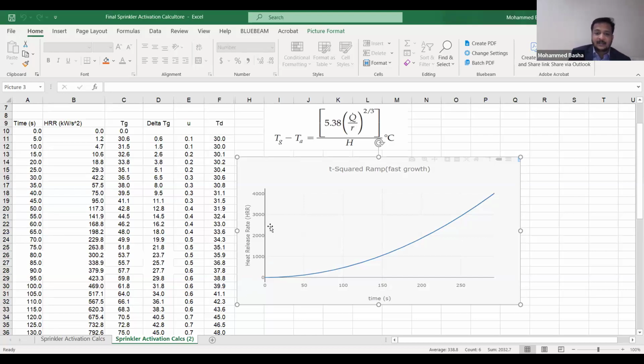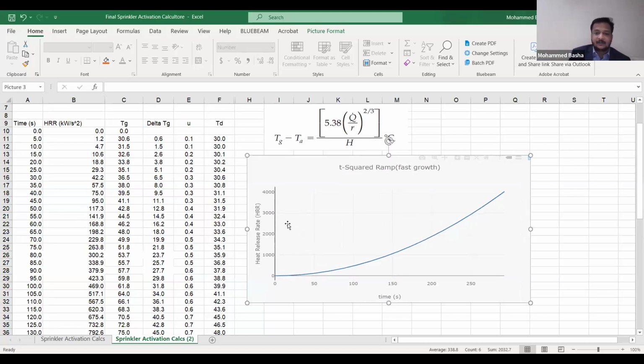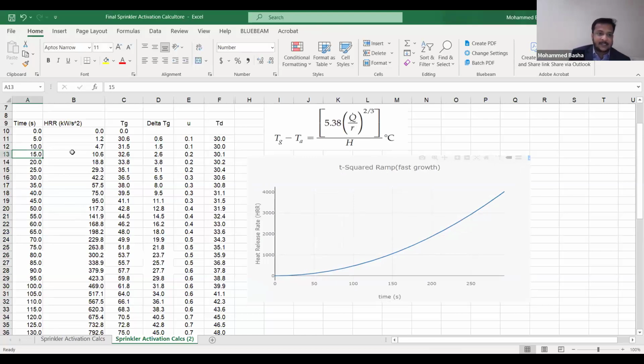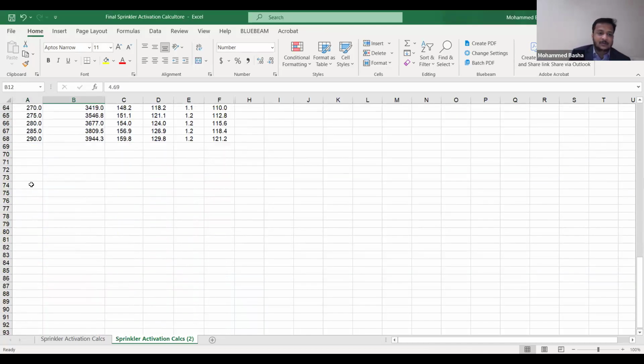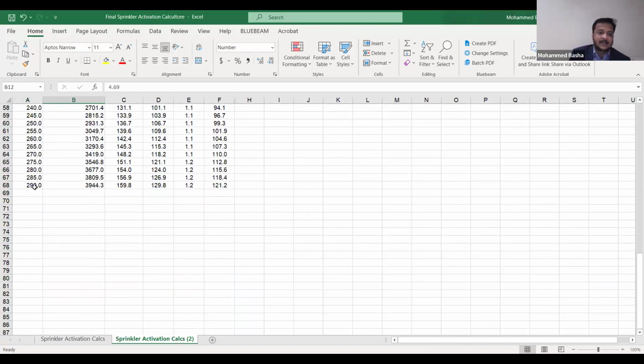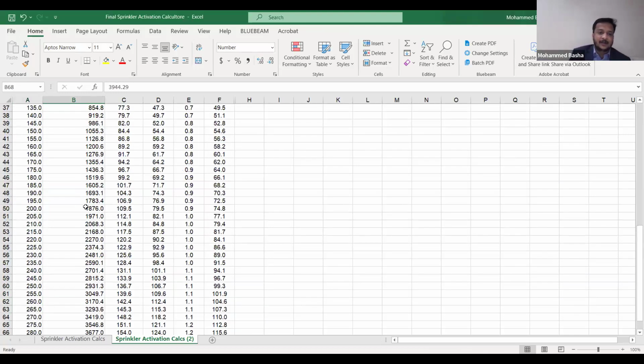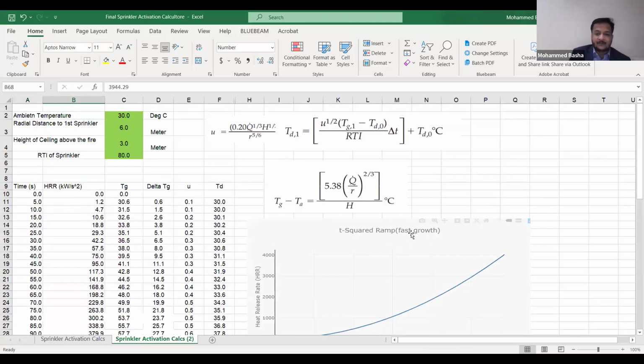So give me the time values and corresponding HRR values. This website gives me this curve, and I have interpolated the graph into time and HRR values. You can see at 10 seconds, 4.7 kilowatt. It goes further up to 4 megawatt. At 290 seconds, it reaches 4 megawatt. So this is the growth of a fast growth fire. These values will change for medium growth, slow growth and ultra fast, everything will change.